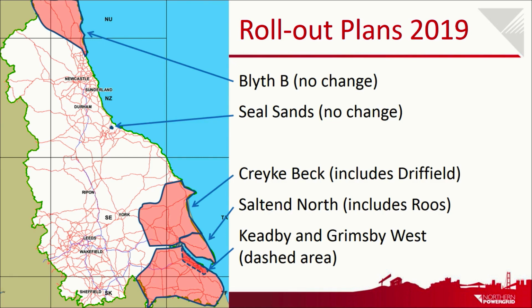We can see the existing areas already here, but a key change is that the Driffield scheme has got bigger in this map. We're rolling that scheme out to incorporate the whole of the network fed from the grid supply point that Driffield's connected to. Because that's the existing Driffield scheme, we can do that without needing a new controller, so the incremental cost to get started on that network will be relatively low. I'll talk more about that in a minute.